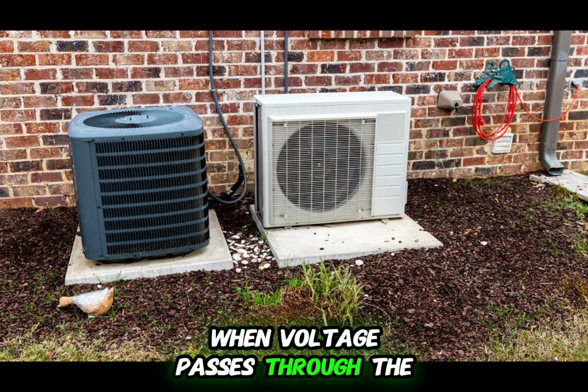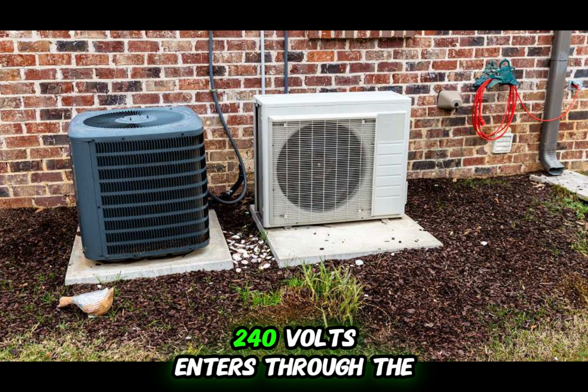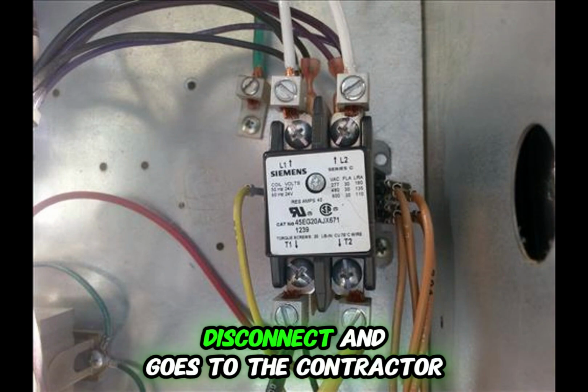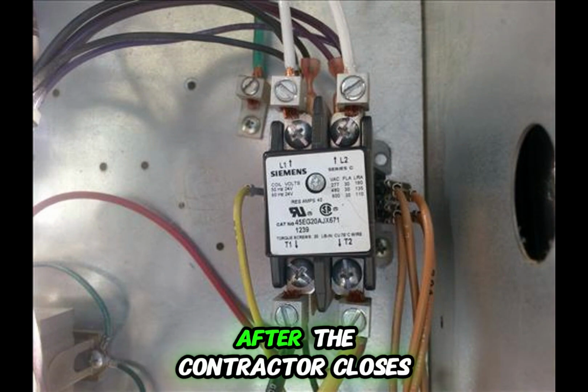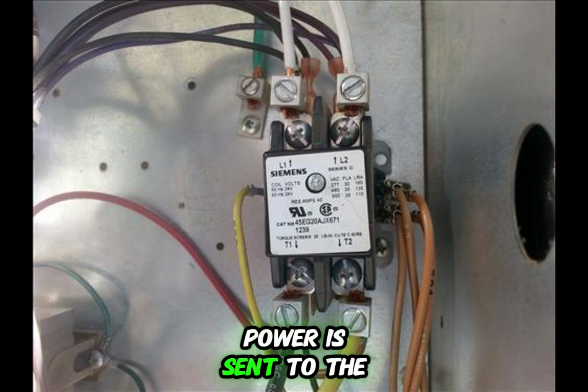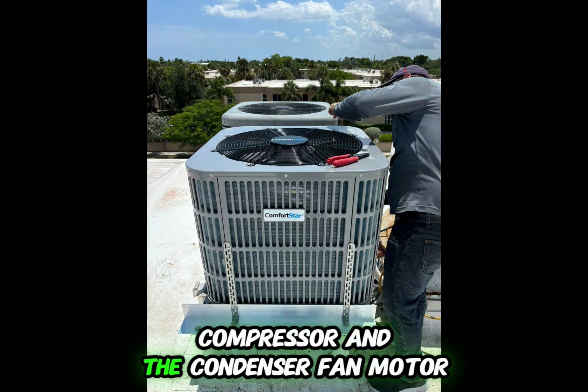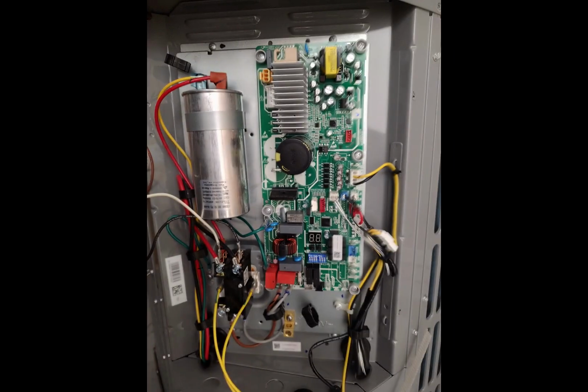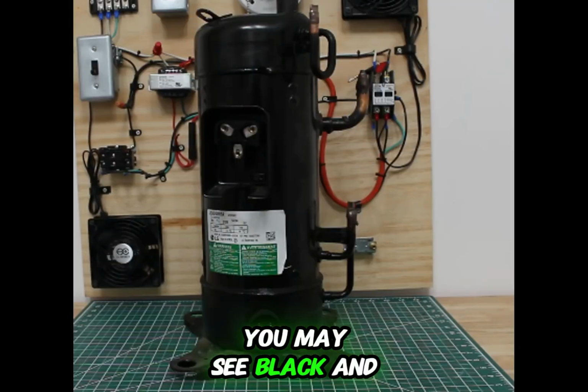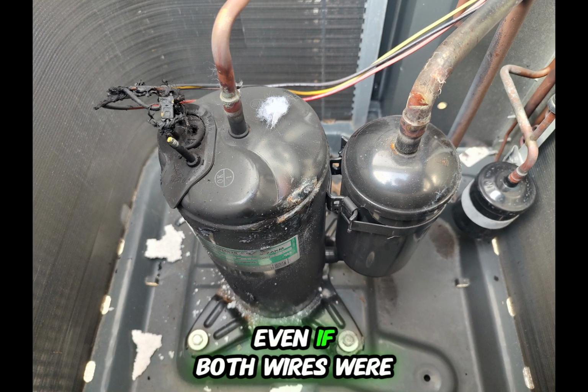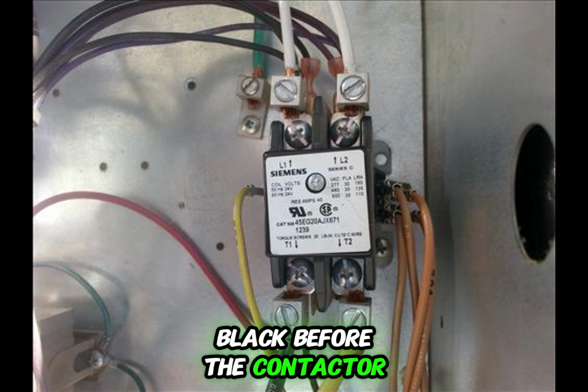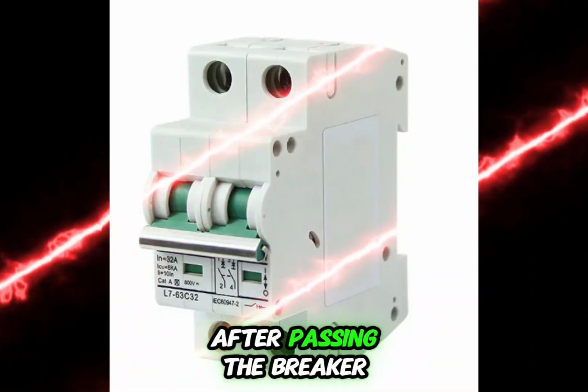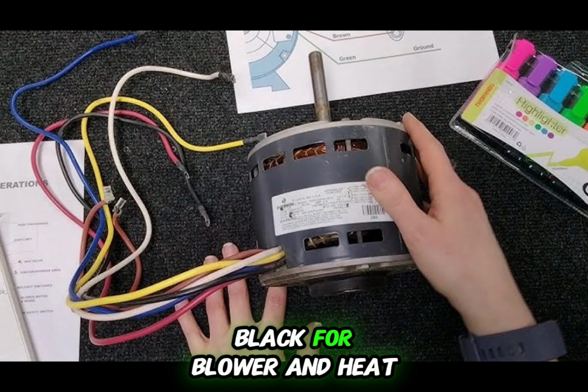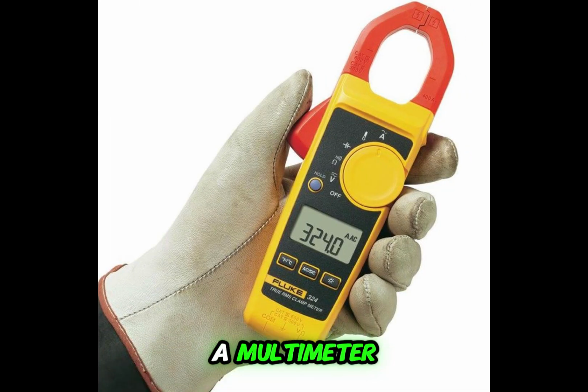When voltage passes through the contactor in the condenser, 240 volts enters through the disconnect and goes to the contactor. After the contactor closes, power is sent to the compressor and the condenser fan motor. At this point, wire colors often change. Inside the condenser, you may see black and red going to the compressor, even if both wires were black before the contactor. Same for the air handler. After passing the breaker, you might see red and black for blower and heat strip connections. But don't assume, always verify with a multimeter.